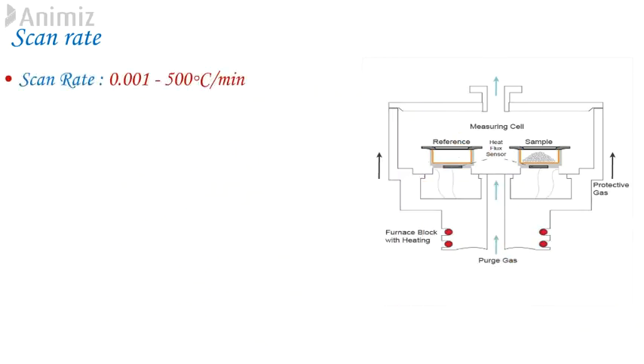11. Scan Rate. Traditionally, most common scan rate used by thermal analysts is 2 to 10 degrees Celsius per minute. But with commercially available instruments, rate can be varied between 0.001 and 500 degrees Celsius per minute, often with significant advantages. The choice of scan rate affects the following areas.